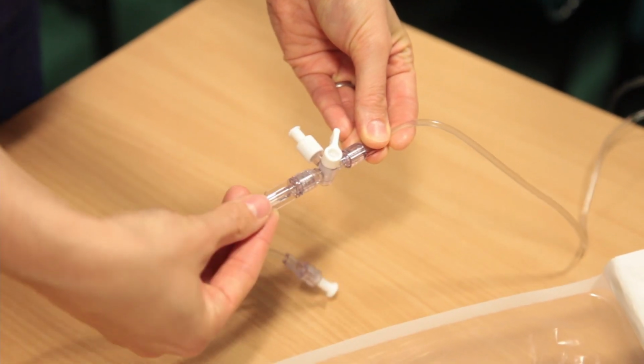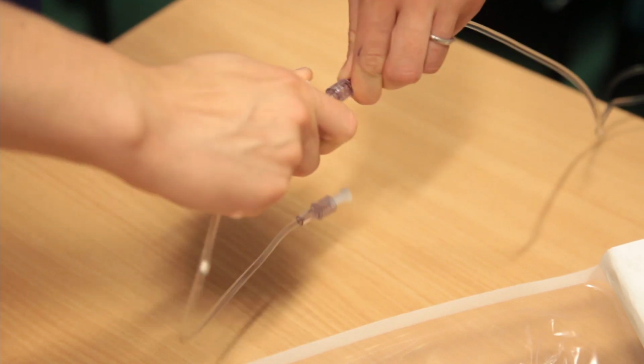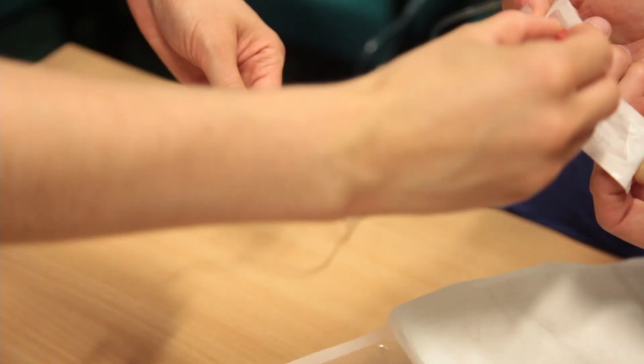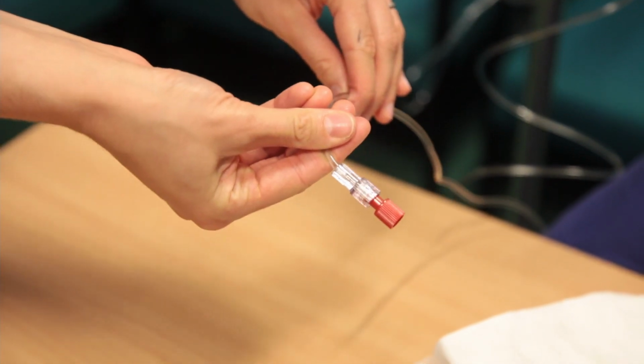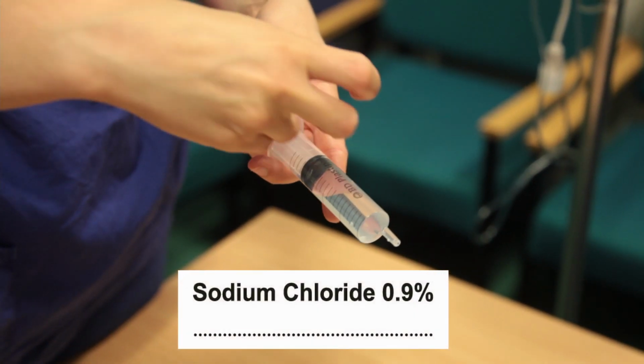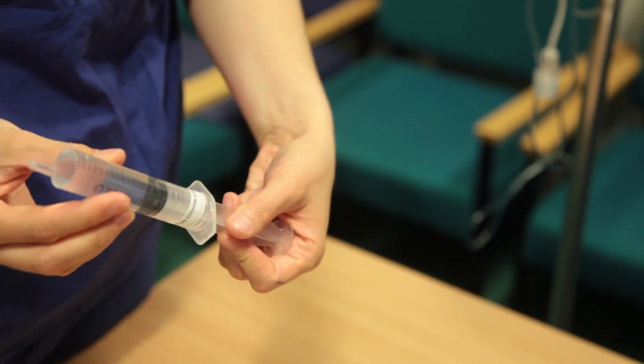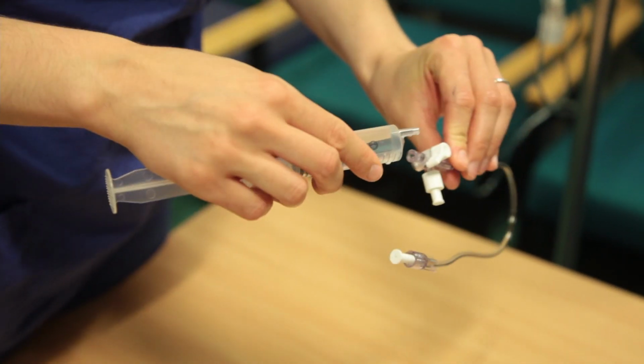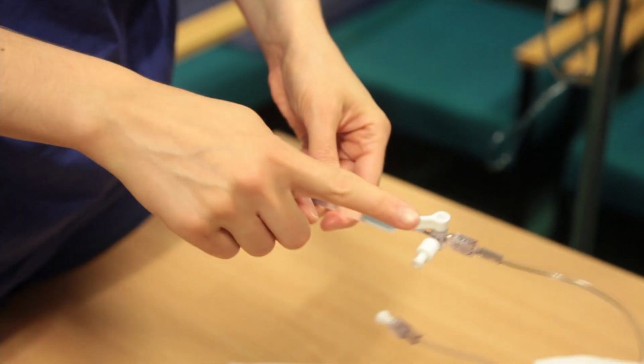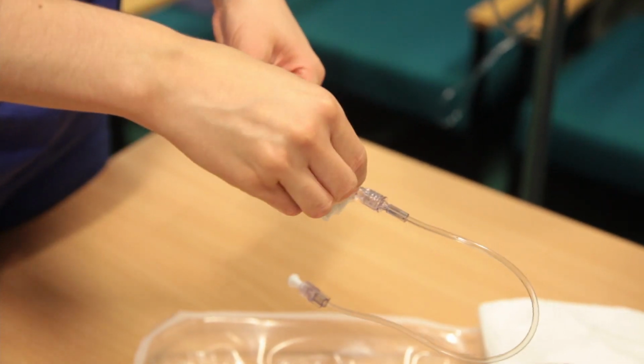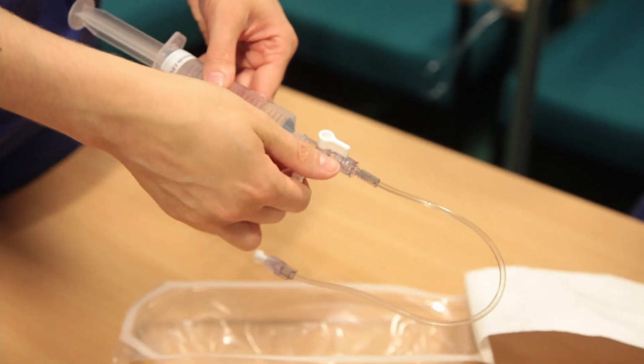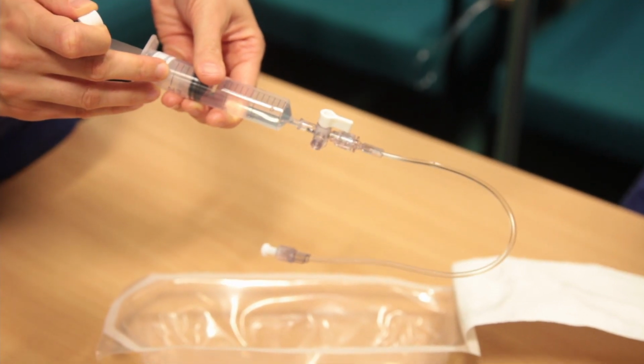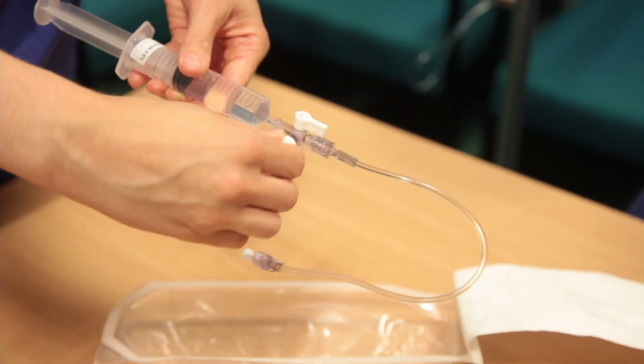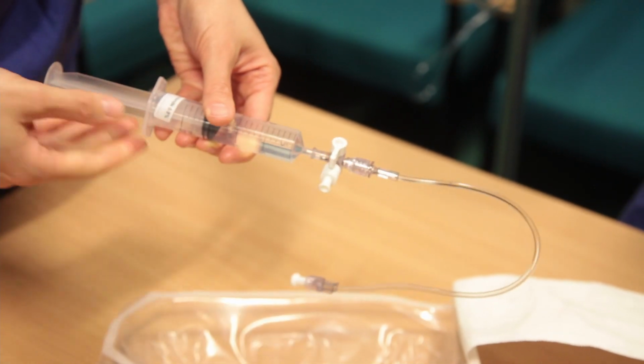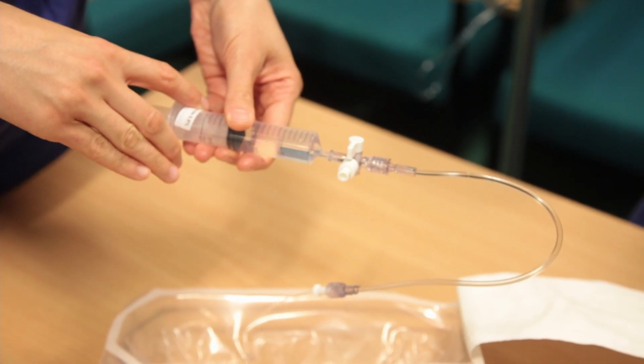Disconnect the final portion of the arterial line set, and we're going to ensure it's prepared for use. Cover the remaining end of the line with a bung to maintain sterility. Ensure all syringes in use are labelled. Flush the final bung port of the line portion you removed. This can be done by turning the off arm to face away from the syringe as shown, and finally that is to eliminate air from this bung port. Then turn the off arm towards the port and flush the last bit.